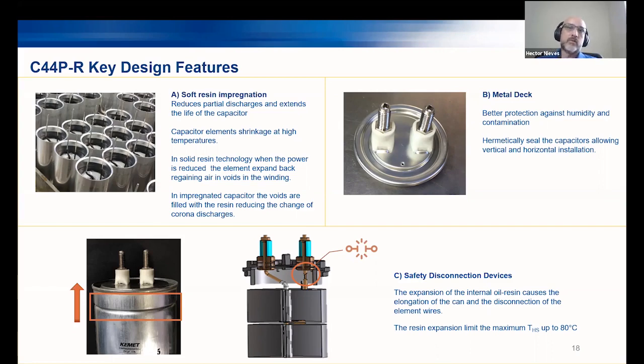So more problematic is the situation you saw before in some of the slides for the failure analysis. It could start degrading the metal, the zinc metal of the metallization. In this case, the resin is doing that. It's not allowing the capacitor to absorb air close to the metallization of the element. So instead of absorbing air or humidity, it will keep the resin together there and less chance of corona. Another advantage of the soft resin or liquid resin is that it has a better performance on releasing the heat of that capacitor when it's overheating on ripple or high harmonic content situation.